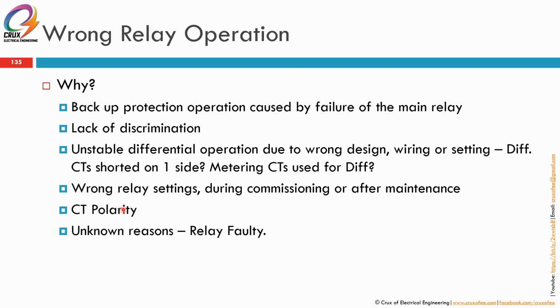But if it is a fault using a summation CT, then CT polarity is an issue because it will sum up all the 3 or 4 CTs. So if one of the CTs' polarity is wrong, you will always have a spill or residual current going through your fault relay.